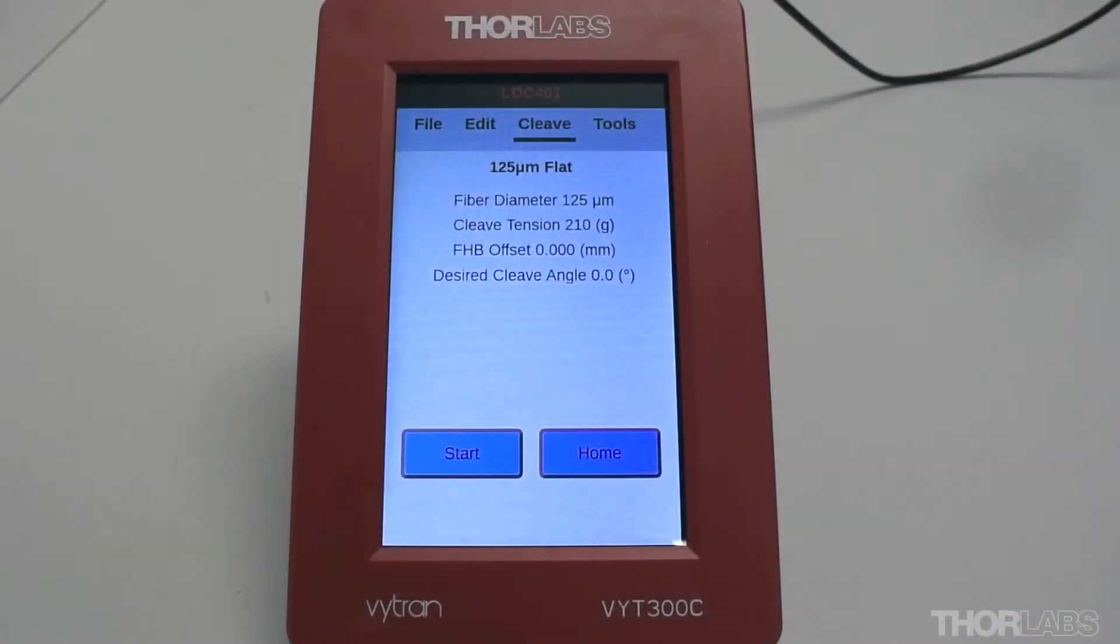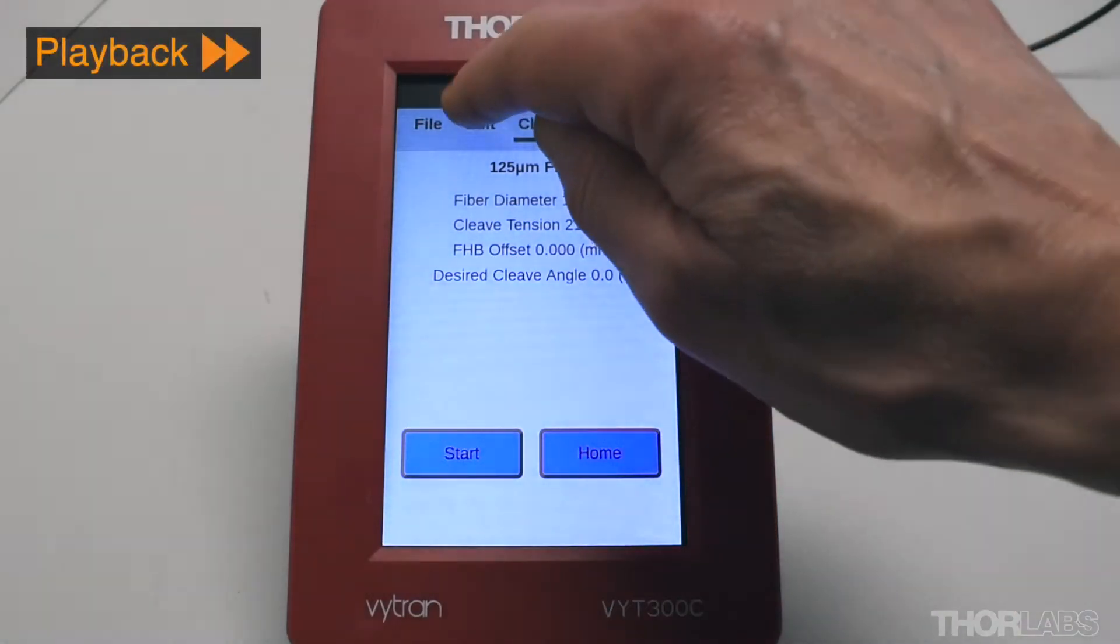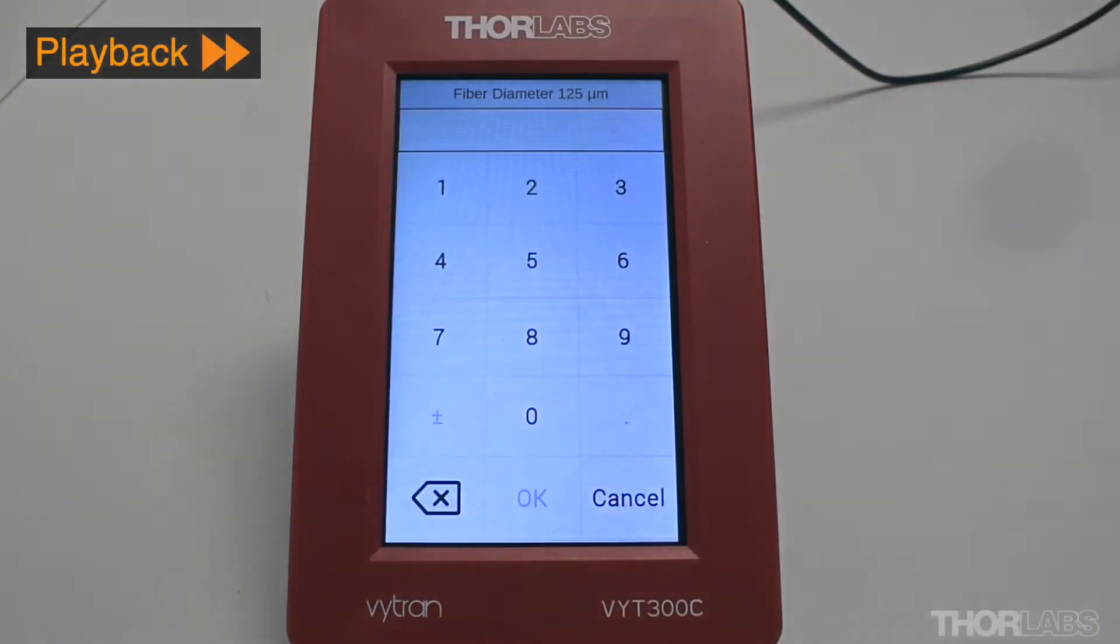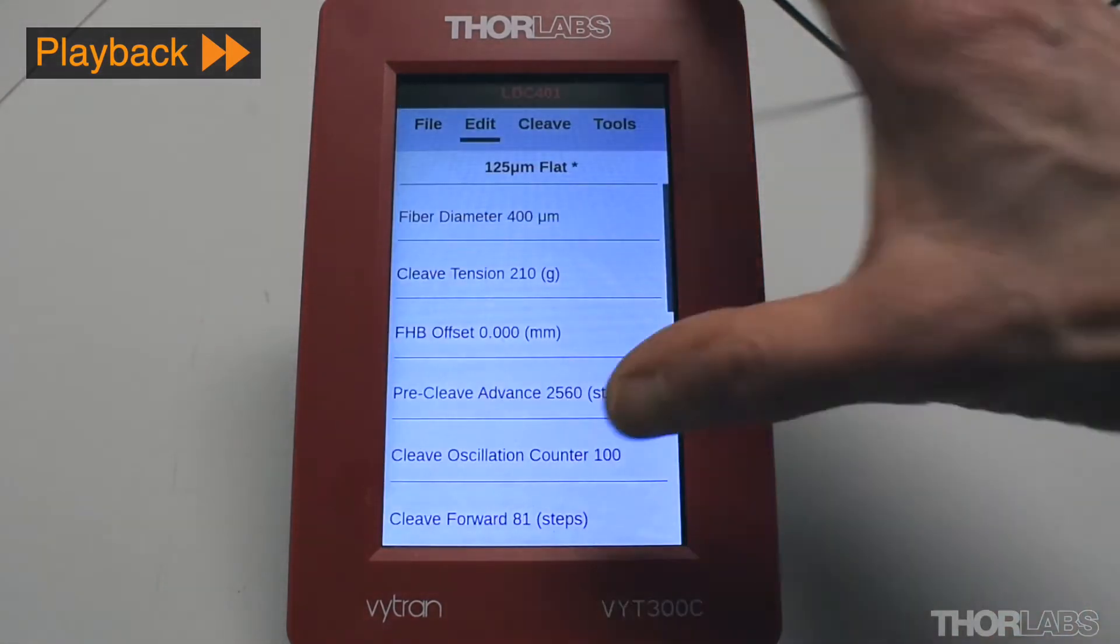If you are performing the angled cleave for the first time, it will be necessary for you to use the handset controller to set up a new file. Input the fiber diameter and clamping distance.